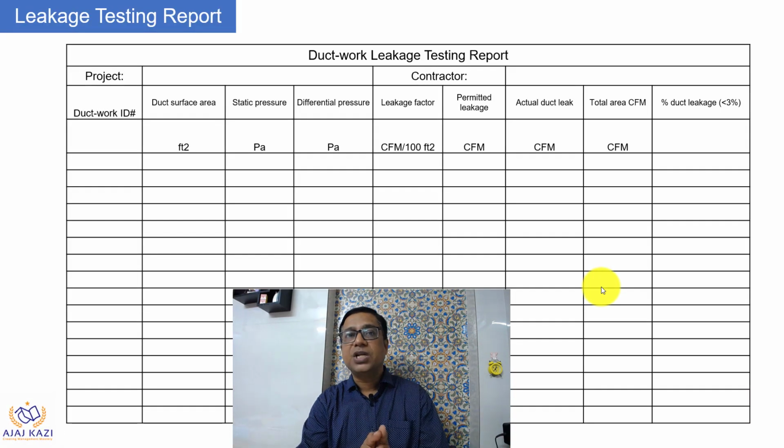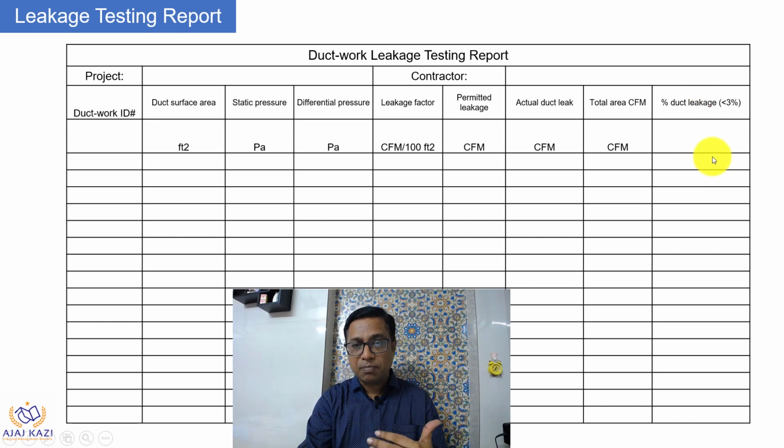We have seen the duct leak testing report in the last video. Remember I said if the percentage of duct leakage with respect to this class is within 3%, you can pass. But what happens if it is more? That is where this video will help you.